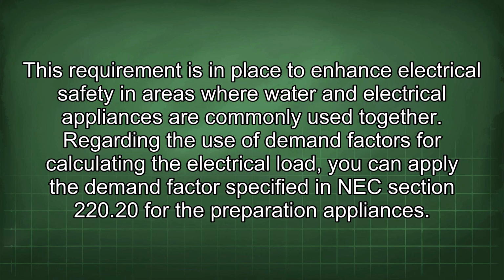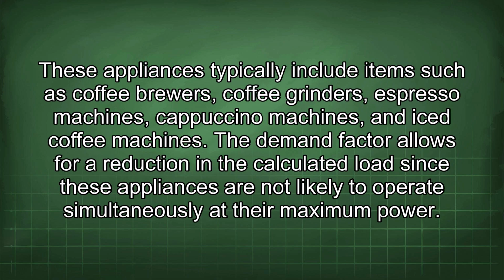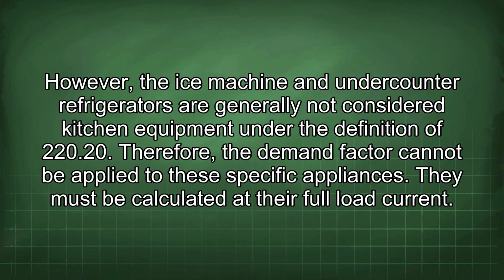Regarding the use of demand factors for calculating the electrical load, you can apply the demand factors specified in NEC Section 220.20 for the preparation appliances. These appliances typically include items such as coffee brewers, coffee grinders, espresso machines, cappuccino machines, and iced coffee machines. The demand factor allows for a reduction in the calculated load since these appliances are not likely to operate simultaneously at their maximum power. However, the ice machine and under-counter refrigerators are generally not considered kitchen equipment under the definition of 220.20. Therefore, the demand factor cannot be applied to these specific appliances. They must be calculated at their full load current.